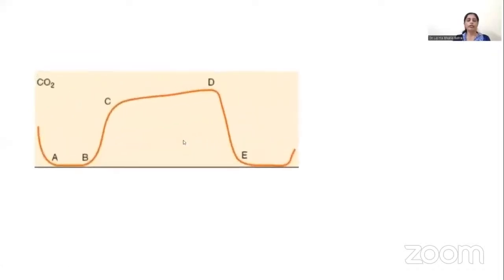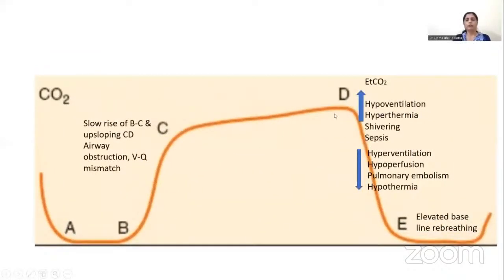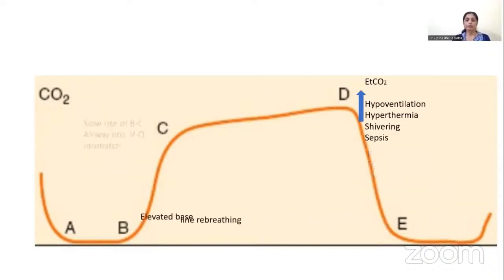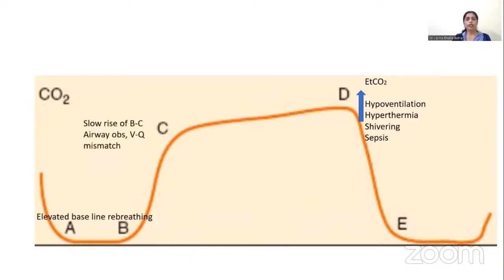The normal capnogram has many shape and size changes that warn of clinical problems. Point D represents the maximum level of carbon dioxide where end-tidal CO2 is calculated. If end-tidal CO2 suddenly drops to zero with loss of the capnogram waveform, it may indicate disconnection of the sampling line or a potentially life-threatening situation such as acute severe hypotension, massive pulmonary embolism, circulatory arrest, or displacement of the endotracheal tube into the esophagus. Adequacy of pulmonary ventilation should be checked immediately. If the baseline does not return to zero, re-breathing of expired gases should be suspected.